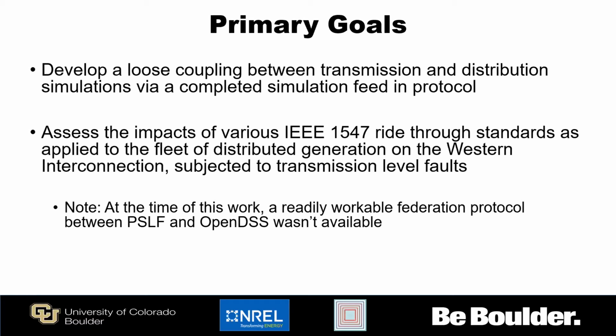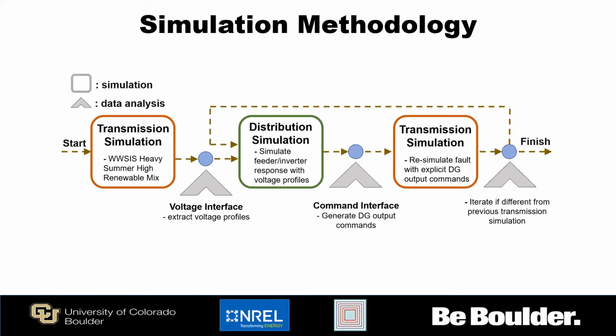So at the time of this work, there wasn't a federation protocol between PSLF and OpenDSS. And so what we did was we created this simulation methodology, and basically we'll run the transmission simulation under some different scenarios. And then we will extract the voltage profiles from the local buses and then send those into the distribution simulation at the feeder head. This allows us then to assess the impact on the DG. Does it trip off? Does it not trip off? And then we can feed that back through into the transmission simulation so that corrective actions can be taken if there is a loss of this distributed generation. So we can do this in a couple different orders.